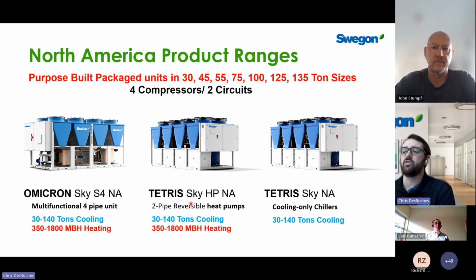So we opted to call this a multifunctional unit because it's a key differentiator, whereas with modular heat pumps, if we have unbalanced loads in our building, we might not be optimizing the heat recovery. We could have some modules in heating and others in cooling. So that's one of the drawbacks with modular type products, where we're not always guaranteeing that we're doing heat recovery. For us, with the way the product's designed on the refrigerant side, the coils on the machine are basically being used as condensers or evaporators if we're heating dominant or cooling dominant. So we're always performing that first level of heat recovery on the hydronic side of our hot water and chilled water system, and only rejecting excess BTUs from the building or absorbing additional heat when we're heating dominant.